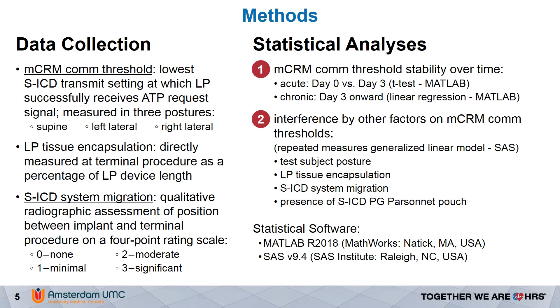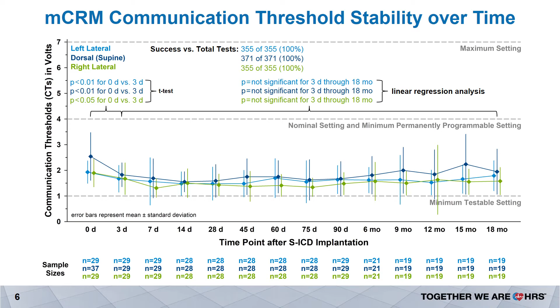Here are our main results. Device-device communication was successful in all 1,081 attempts performed in 37 canines within the study. Communication thresholds were low and stable throughout follow-up. Only 8 individual measurements exceeded the 4.0 volt nominal setting, each of which was observed in only a single posture for that given follow-up time point, and each of which decreased to a value below 4 at the next follow-up time point. A statistically significant but clinically not meaningful decrease in communication threshold was observed between implant and day 3. No statistically significant difference was observed from day 3 throughout month 18.